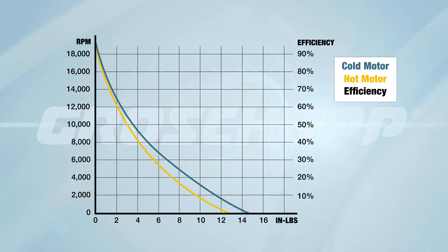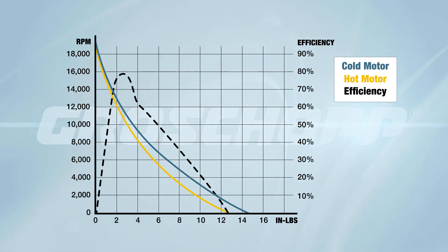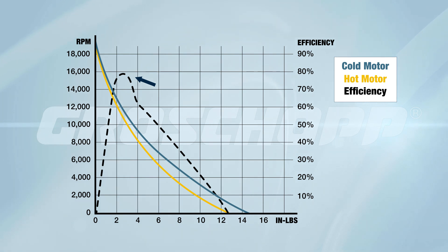Now we've added the motor's efficiency curve, shown as the black dashed line. Under ideal circumstances, the motor's peak efficiency will occur very near the motor's operating torque. However, in most cases, the actual peak efficiency will occur at higher torque than the rated torque.